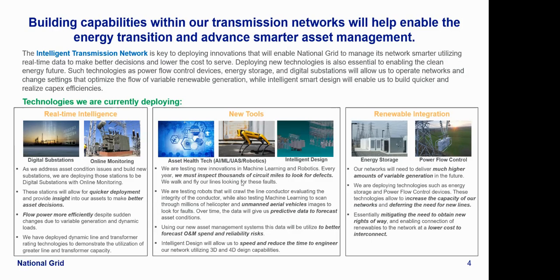That works for a few transformers, but once you, like National Grid, adopt this for every single transformer, that brings up another issue: you can't just rely on one live platform. This needs to be a centralized database where all the information from all the transformers comes together, and the technicians have access to that centralized point.